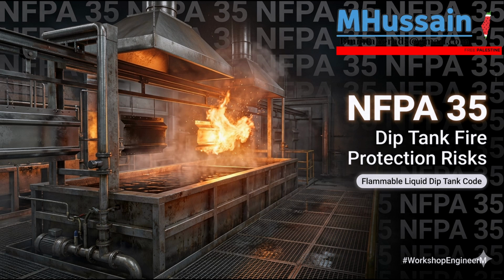Right. This is a classic secondary disaster scenario. If the floor drainage system isn't mathematically sized to handle the sheer immense volumetric output of the fire suppression systems, the building rapidly floods. And because many flammable organic solvents are physically lighter than water, they float. So the burning fuel literally floats on top of the rising sprinkler water. Precisely. The burning liquid rides the crest of the flood, flowing out the doors, down the hallways, and spreading the fire into areas of the plant that were completely unaffected. Well, it's a nightmare. The drainage facilities must be rigorously engineered to handle the massive volume of the fire protection system discharge, routing that contaminated burning water through interceptor trenches to a safe remote containment basin on the property.